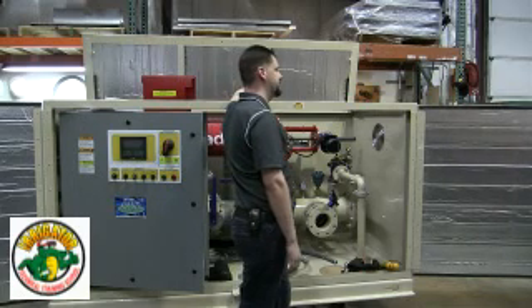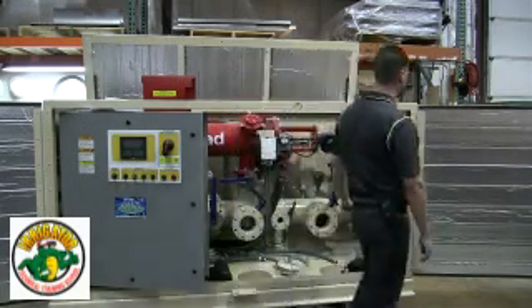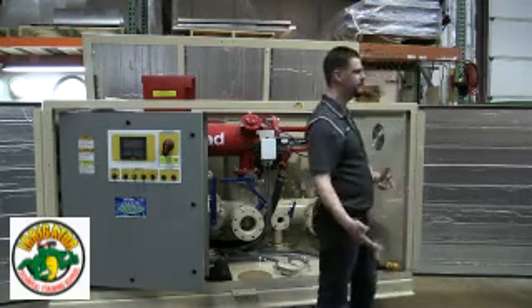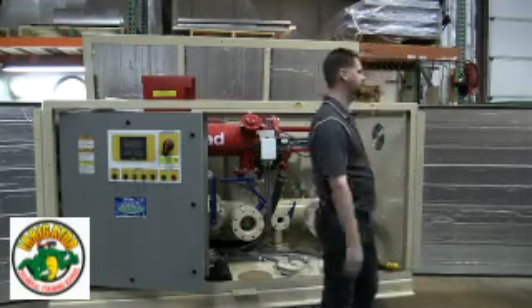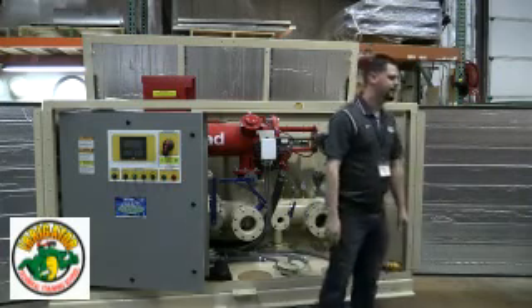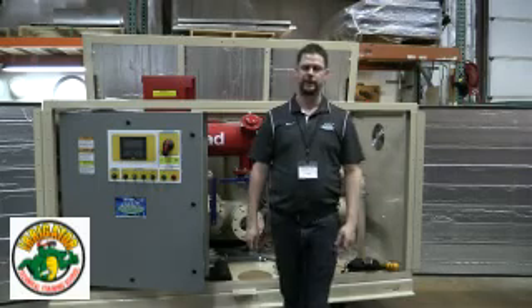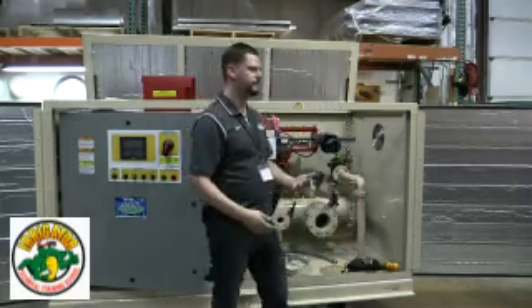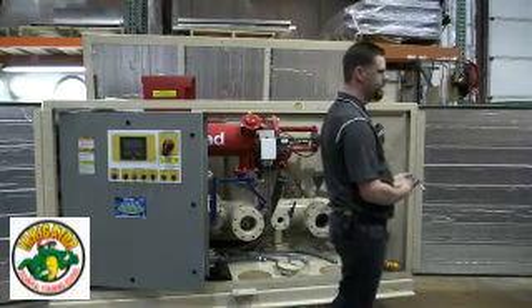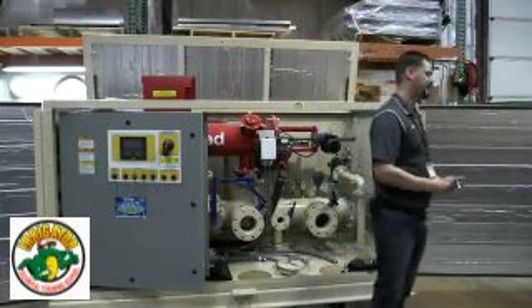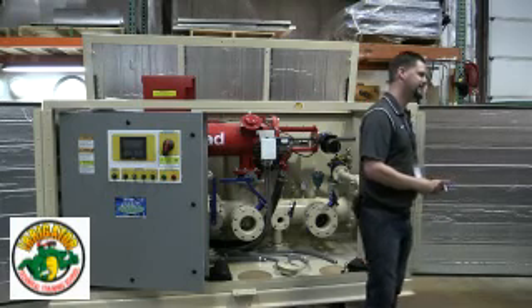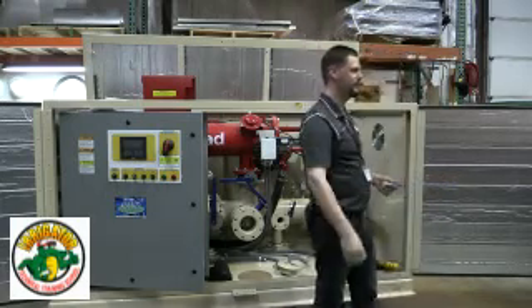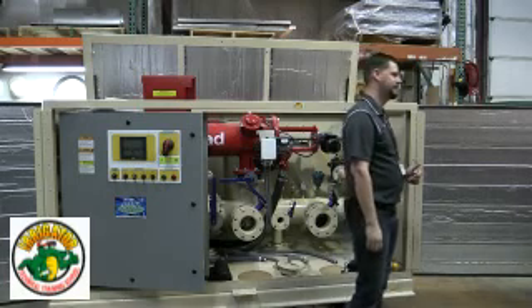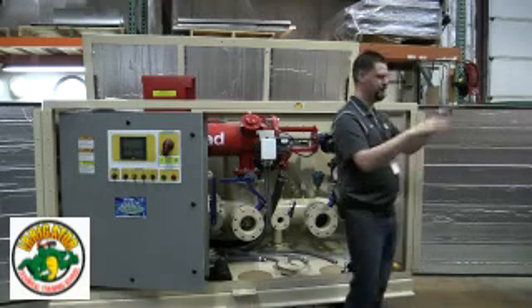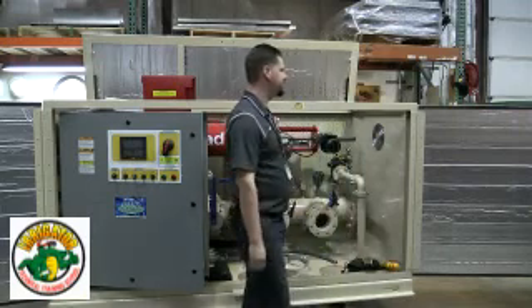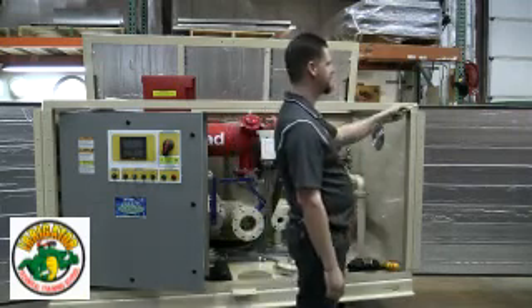asked by one of our bigger recent pump station customers if we could come up with an emergency parts list, because they can't be down for any amount of time or else millions of dollars, right? Fish farm? Yeah. So after they got this list together, like fuses and transducer and stuff like that, I'm like, what about a diaphragm for the pressure relief valve? Because if that won't shut, I mean, you can't pump water up a 200-foot cliff if you don't have pressure. They said, oh, there's a valve in front of it. And I'm like, oh, all right, never mind. Because without that valve in front of it, they would be screwed, right?